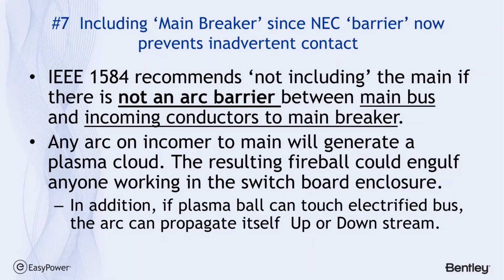This is a real common mistake because there's a lot of confusion, especially based upon our understanding or misunderstanding during the 2002 standard. And that is, the IEEE 1584 recommends not including the main if there's not an arc barrier between the main bus and the incoming conductors to the main breaker. The problem is any arc on the incomer to the main will generate a plasma cloud, and the resulting fireball could engulf anyone working in the switchboard enclosure. In addition, if the plasma ball can touch electrified buses, the arc can propagate itself up or downstream. And this is not an exaggeration. There's many videos on YouTube that verify this very problem.